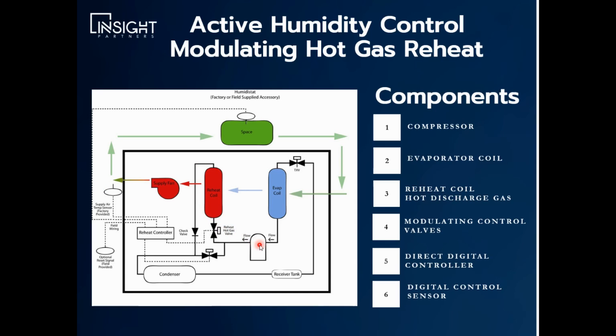So what we do is we take some of the gas coming off the compressor and instead of sending it to the condenser, we send some of it to a reheat coil. This generally uses a controller — which is shown here — that measures the space temperature, looks at the supply temperature, things like that. It controls — used to be a two-valve system, but now it's just a three-way valve, same premise. It controls the hot gas reheat coming here. So as the air blows across the evaporator coil, cools down, hits the reheat coil, and we send enough gas there to reheat it to the desired temperature required in the space to meet the space load. So that's modulating hot gas reheat.